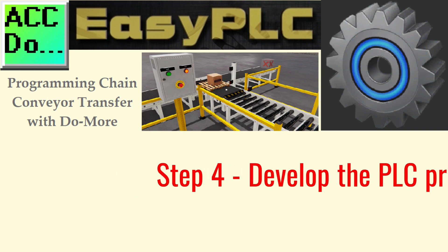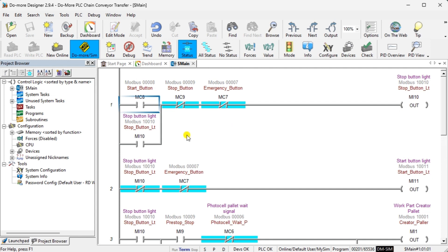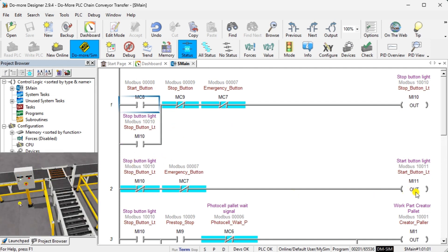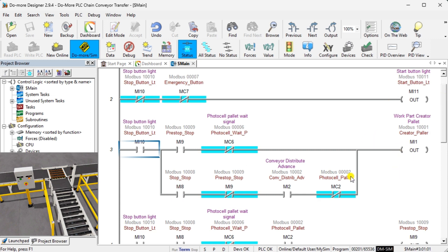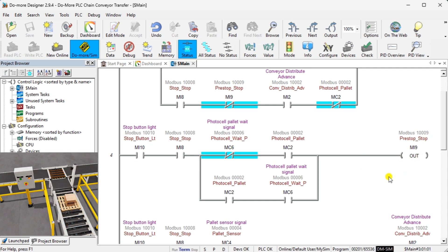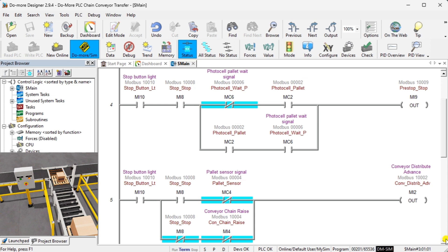Step 4: develop the PLC program. Writing the ladder logic for our PLC example will be the next step in our program development. The chain conveyor transfer starts and stops via the sealing circuit for the stop button light, and our stop button light contact will control the rest of the ladder. The start and stop lights are off when emergency stop is activated, indicating to the operator that emergency stop must be reset. The pre-stop operation will control when the skid moves onto the belt conveyor. The conveyor distributes and advances the belt conveyor based on the pallet sensor and chain rising signal. The stop barrier will separate the skids as they transfer from the belt to the chain conveyor.